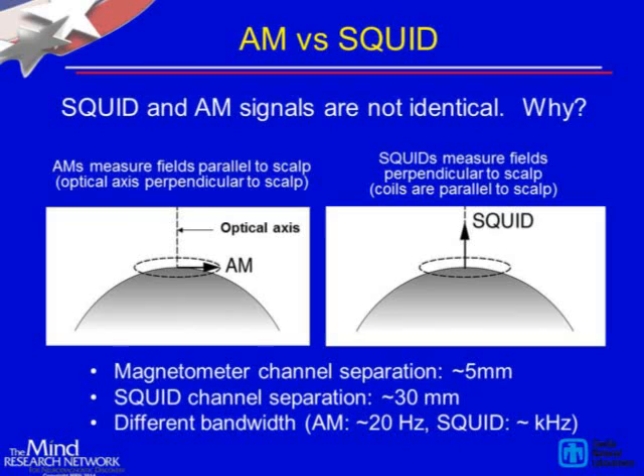One of the primary reasons why we think we don't see the same signals from both the atomic magnetometers and the SQUID system is that we're measuring different components of the magnetic field. The SQUID system measures the so-called radial component, the field component that sticks away from the head, whereas we're measuring field components that are transverse to the skull, the scalp. Because of that, we shouldn't expect to see exactly the same signals.